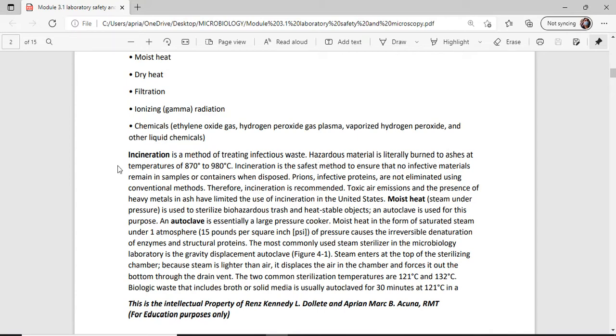The temperature for your incineration is 870 to 980 degrees Celsius. Incineration is the safest method to ensure that no infected material remains in the sample or container when disposed of. Prions are very infective proteins and are not eliminated using conventional methods like disinfectants. That's why you do incineration, to totally burn everything and kill all the microbes. Therefore, incineration is recommended, but the concern is that it produces toxic air emissions and heavy metals in the ash, which is why it has limited use in the United States.